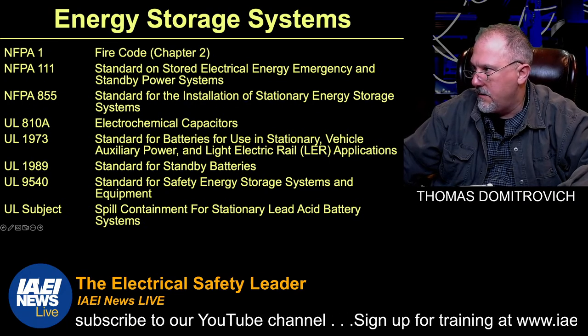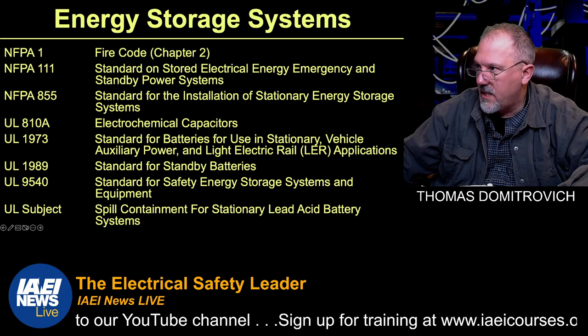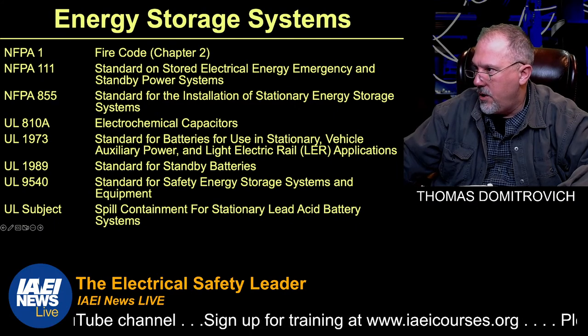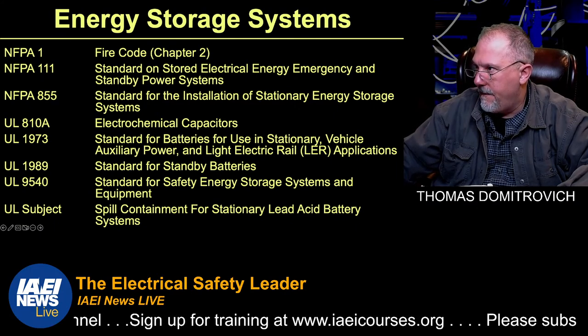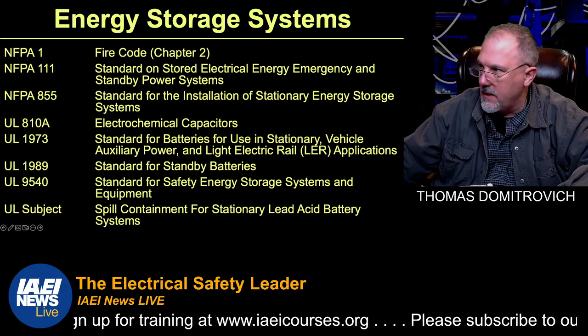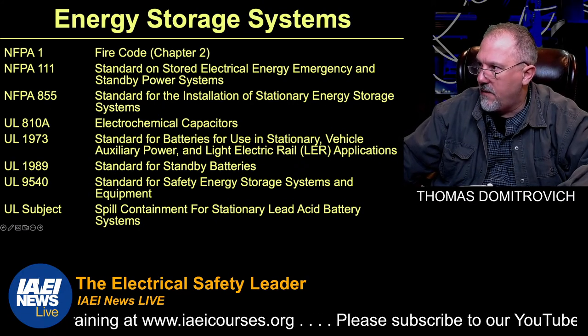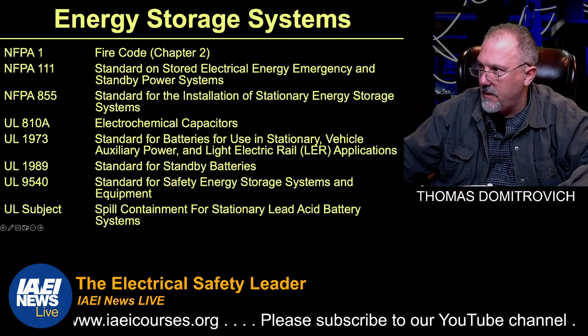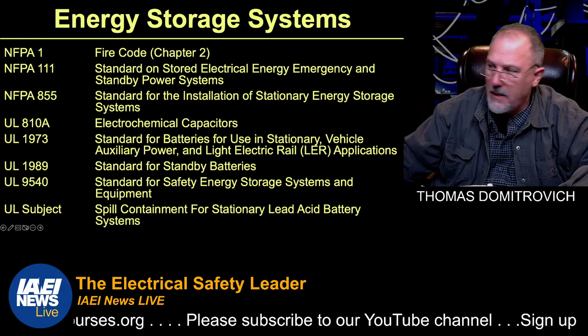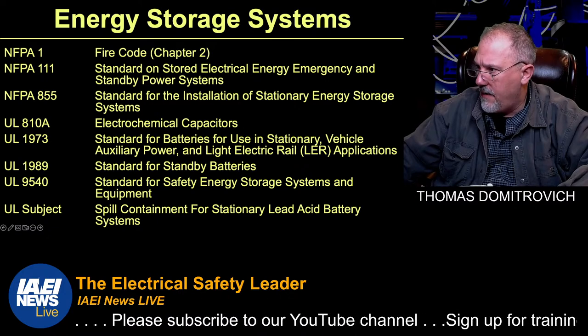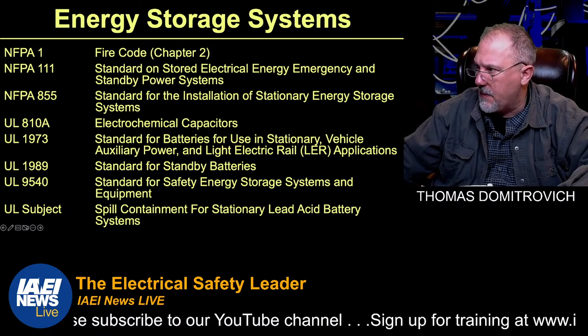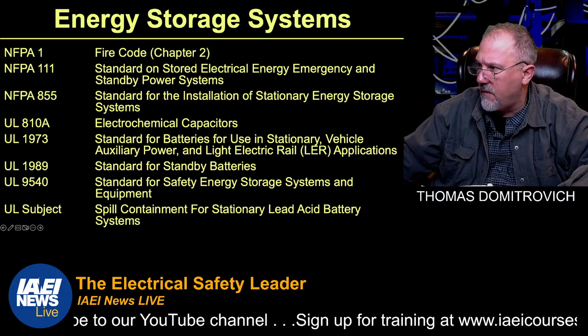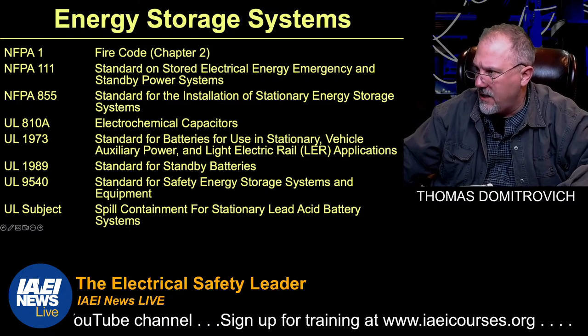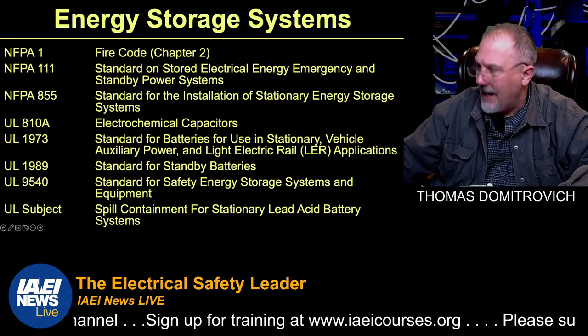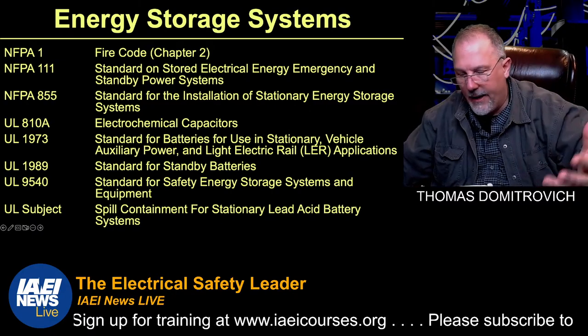Oh boy, 26.3.5.2.2, which 26.3.5 is facilities. 26.3.5.2 is your subsidiary station buildings of those portions. And then the subsidiary facility shall be inspected at least monthly by central station personnel for the purpose of verifying the operation and condition of all supervised equipment, telephones, energy storage systems, etc., etc., etc.